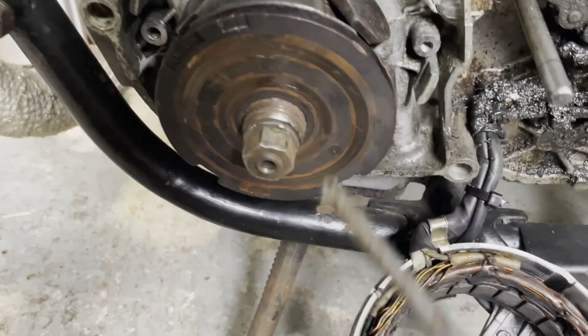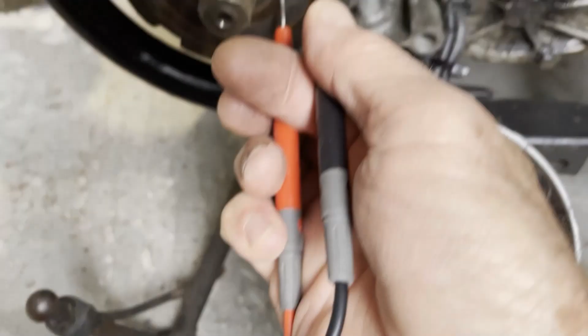Here's your rotor. You can test it by going across these copper tracks, if I can manage to do it one-handed. Again, meter on the ohms range, 200 ohms range. That's showing over limit or open circuit, but in my case, sadly, the shiny bits of the copper track are where the brush has been rubbing, but I've got my probes on those two shiny bits and there's no beeping. I'm still over limit because my rotor has for some reason gone open circuit. So that, I think, is our main problem.